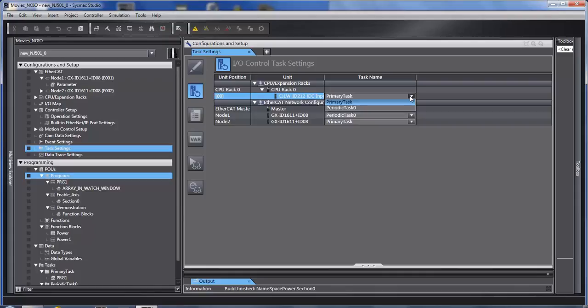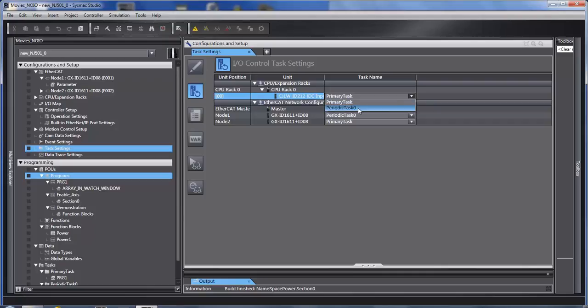Again, why do we do this? So that it doesn't change state in the middle of my task. I would assign it to the primary task to get optimum speed. I would assign it to the periodic task 0 if I didn't want it to change state because periodic task 0 runs much slower than the primary task.